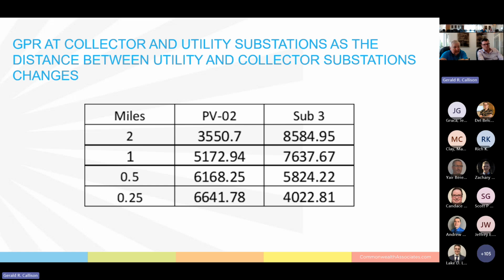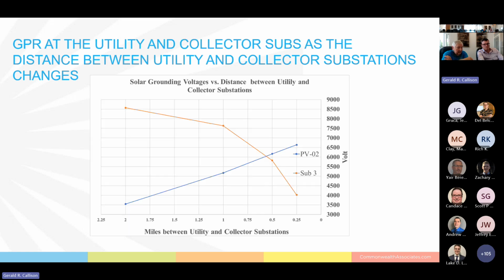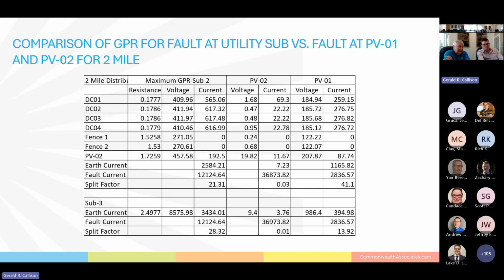And the closer you get the two together, you can see the results that when you get a half mile apart, all of a sudden the collector ground potential rise is higher than the utility substation. You get them really close together. The ground potential rise at the utility sub goes down, but it goes up higher at the collector station. Again, for us visual folks, if you want to look at it on a graph, you can see that the ground potential rise goes down for the sub 3, and it goes up at the collector station. So that's the interaction that we're looking at.